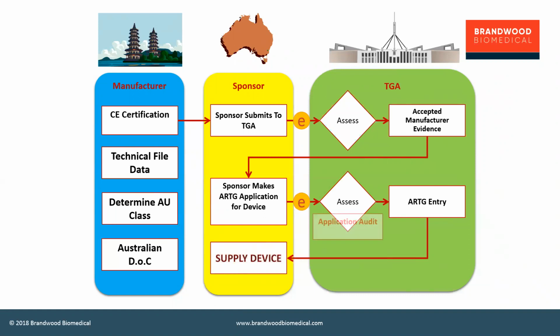The assessment stage, in some cases though, in certain higher risk devices, and for any device, if TGA so choose, can be augmented through an application audit. And that is where TGA specifically requests more information. They will go to the sponsor and ask that the sponsor arrange for the manufacturer to supply certain technical file data and maybe the declaration of conformity for TGA to do a desktop review. This is not a complete conformity assessment. It's simply a desktop review of some of the higher level documentation.